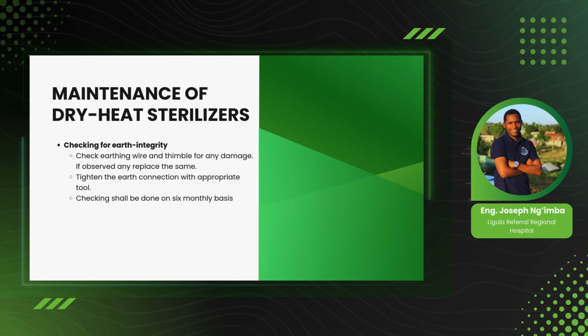So we check if there is any loose connection. We check the earthing wire and the thimble to see that they have a good connection and there is no damage. If you observe that something is not good or is damaged, you will have to replace it. If the earth wire or the thimble is damaged, you will have to replace it. We also check that the tightened connection is appropriate, and we use an appropriate tool to tighten it. This kind of maintenance is done on a 6 months basis.